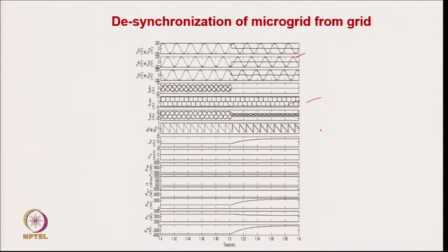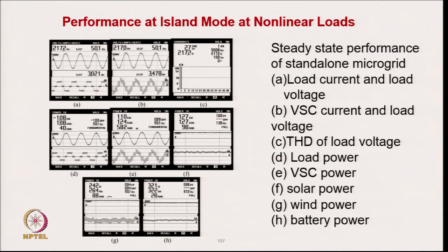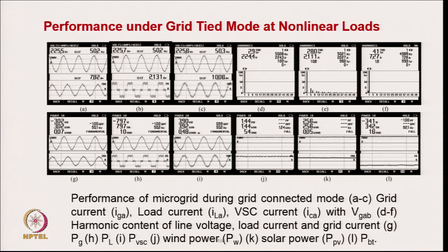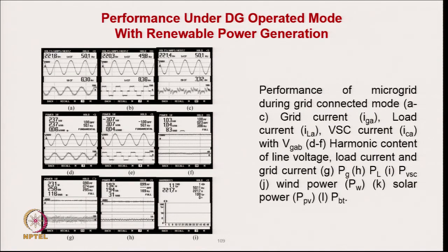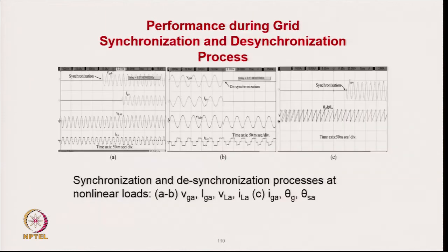In islanding mode, the voltage THD is 2.7 percent even under highly nonlinear load. In grid-connected mode, the grid current THD is quite low. In DG set operating mode, the DG set current, load current, and compensating current provide active filtering, improving power quality on the DG set side. When the grid disappears, load voltage and load current are not affected. When the grid reappears, after a few cycles of synchronization, the grid current starts appearing when the switch is closed. Desynchronization shows that the angle synchronization process is well-managed along with current and voltage dynamics.